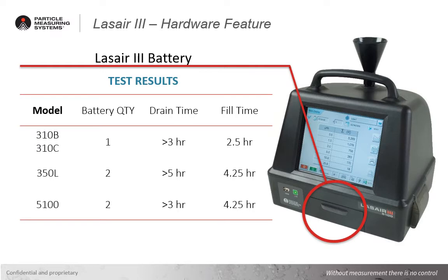With the Lasair III 310 model utilizing only a single battery providing greater than three hours of portable operation, and only two and a half hours to fully recharge. The Lasair III 350 using two batteries has greater than five hours of operational time, and takes about four and a quarter hours to recharge. The Lasair III 5100, again with two batteries installed, greater than three hours of operation, and about four and a quarter hours to recharge.